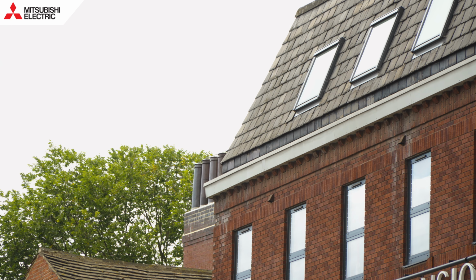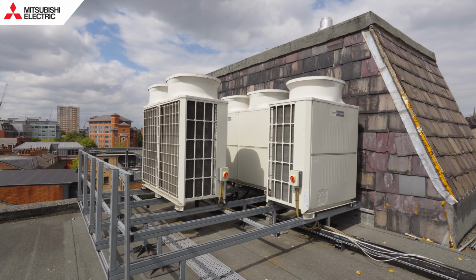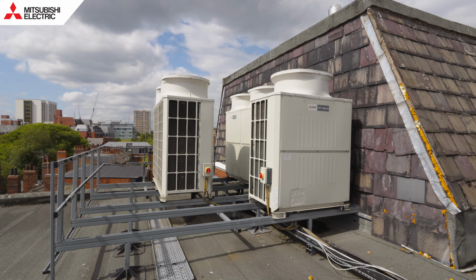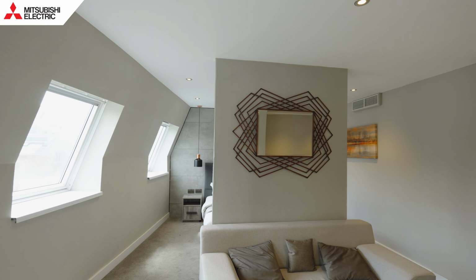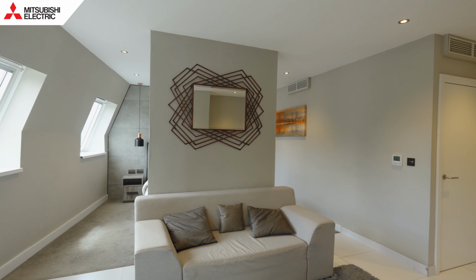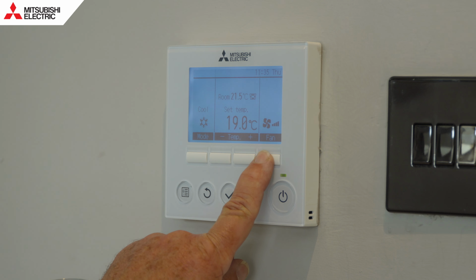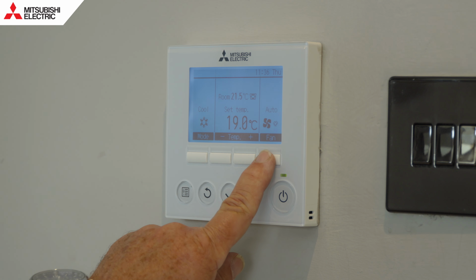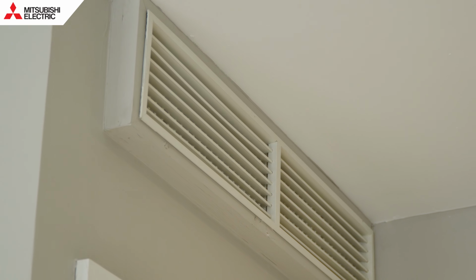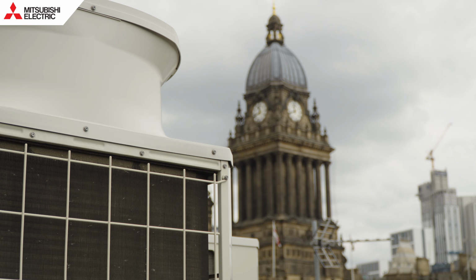HVRF is a two-pipe heat recovery VRF system. You have an outdoor unit, two refrigerant pipes going to a central hybrid branch controller box, and from there just two water pipes going to your indoor unit. The box itself can do simultaneous heating and cooling, giving you the design flexibility of a VRF system and the comfort of a chilled water fan coil unit.